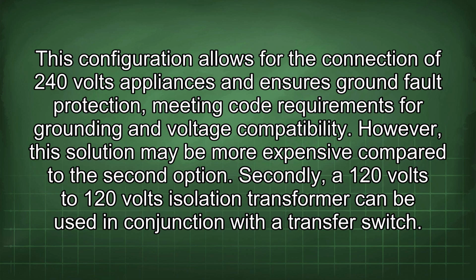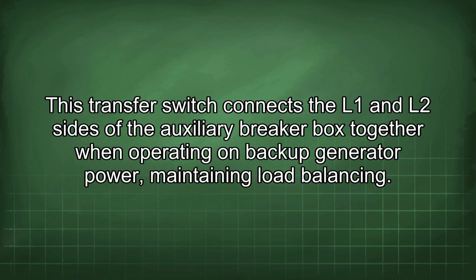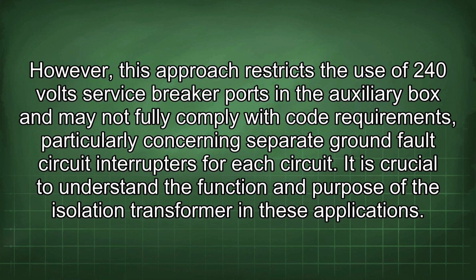Secondly, a 120 volts to 120 volts isolation transformer can be used in conjunction with a transfer switch. This transfer switch connects the L1 and L2 sides of the auxiliary breaker box together when operating on backup generator power, maintaining load balancing. However, this approach restricts the use of 240 volts service breaker ports in the auxiliary box and may not fully comply with code requirements, particularly concerning separate ground fault circuit interrupters for each circuit.